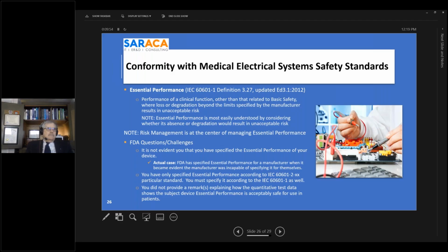So these are definitions, and this is the theme that I wanted to present here: essential performance is the foundation of everything, and it is different from basic safety. The main thing to note is that essential performance and expected service life came to be in edition 3.0 of the 60601, and it introduced risk management at that point in time. So the main story here is that risk management drives your whole design process to make sure that it's safe for basic safety and essential performance.